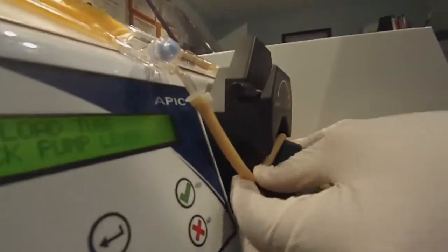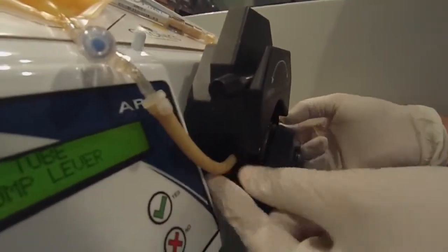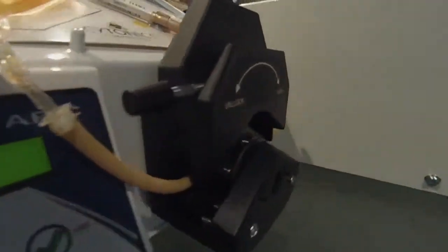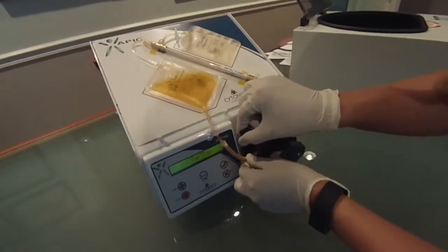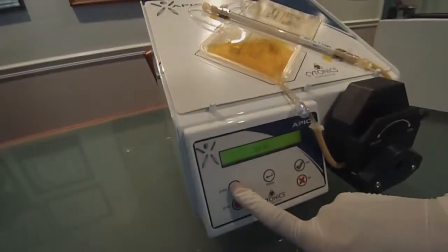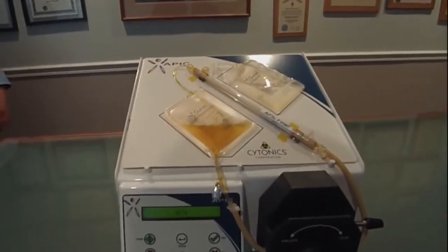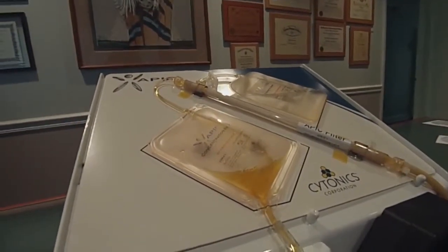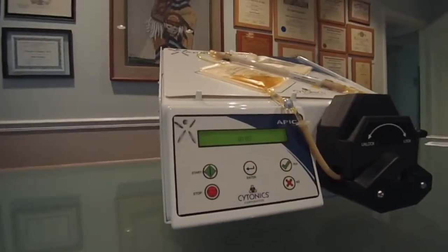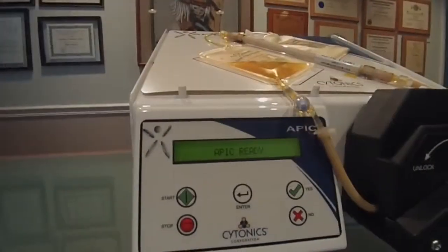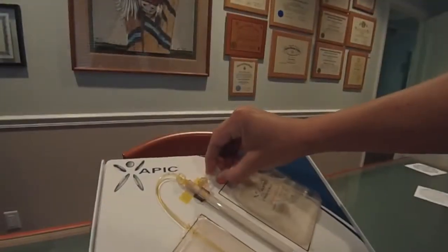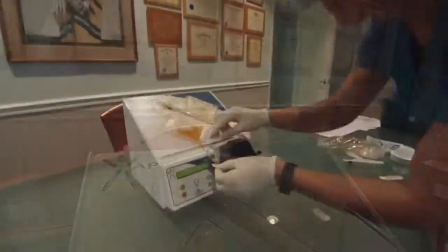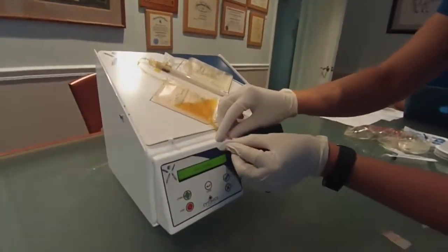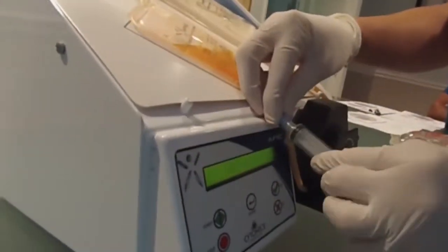Load the tubing into the pump head by securing the tubing between the tubing retainers on each side of the pump head. With the tubing properly secured, lock the pump lever. Press start to begin the 20-minute cycle. The waste bag will begin to fill up as the volume in the concentration bag decreases. Once the cycle is complete, the pump will read APIC ready. Close the clamp on the waste bag and the concentration process is complete. Alcohol wipe the blue port and connect the syringe to withdraw the APIC.